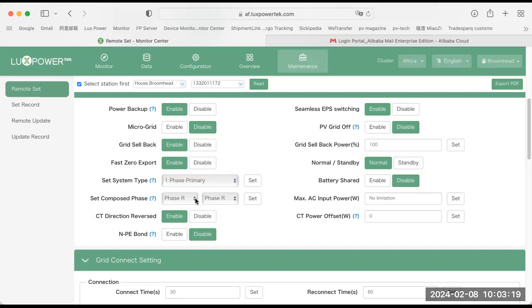On a single phase, it'll come out standard as phase R. But if you're doing an off-grid installation, where the machine cannot detect the phases automatically from the grid, then you have to assign each phase to the machine. In other words, which is the R phase, which is the S, and which is the T phase. And obviously you can change those around once you have a look at things like motors, where you need to change the direction of the motor.